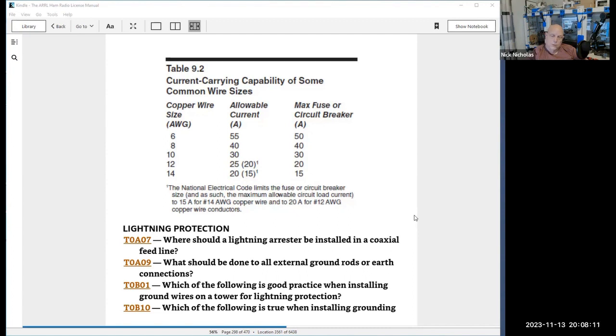Next, all ground rods, all earth connections should be bonded together. And so should every device in your shack. Everything in your system should be bonded, and we'll cover that in just a minute. If you want to ground a tower or a mast, and you should ground them, tie that to ground at the same grounding point as your electrical ground and all the rest of the ground systems. Now, that may mean that you'll have to run a cable to it to ground it, and that may mean you need a big wire to get to it.